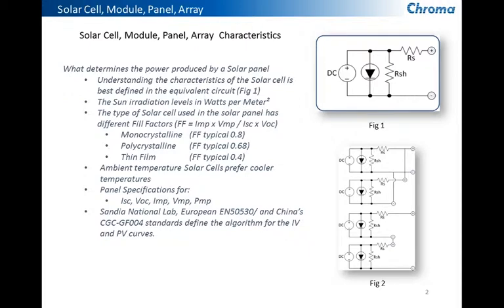There are panel specifications. There are some parameters that are specific for defining solar panels. There's a short circuit current and open circuit voltage. There's a current at maximum power, a voltage at maximum power, and then the maximum power output rating itself. These parameters can be used in an algorithm to create what's known as a voltage and current or an IV curve and a power and voltage or PV curve.